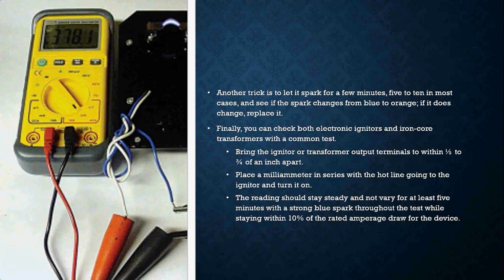And finally, you can check both electronic igniters and iron core transformers with a common test. You can bring the igniter or transformer output terminals to within a 1/2 inch to 3/4 of an inch apart. You can place a milliamp meter in series with the hot line going to the igniter and turn it on. The reading should stay relatively steady and not vary for at least 5 minutes, with a strong blue spark throughout the test, while staying within 10% of the rated amperage draw for that device.